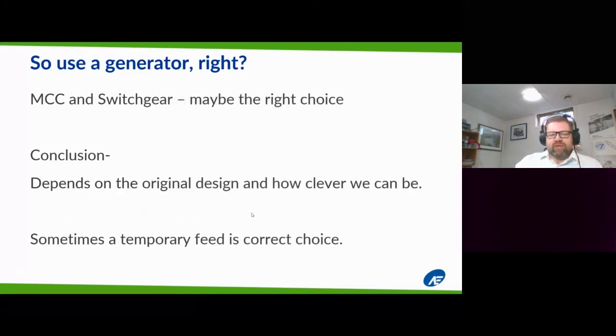For MCCs and switchgear, we typically use a generator or another feed. Going back to the 5 nines discussion, if we have a main-tie-main system, we can provide power without having the generator connected, backfeeding and finding clever ways of feeding the facility. So a generator might be the right choice, but probably not for a panel. The key is if you design your facility right, your MCC and switchgear, you can probably backfeed and find clever ways of figuring your loads.